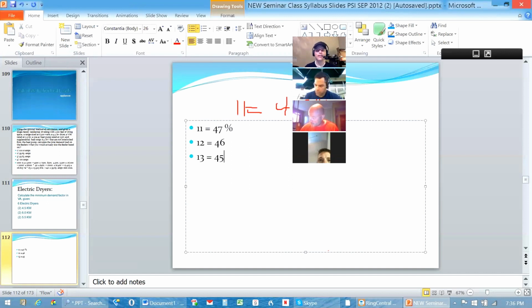So I'm just going to take the net number. If they gave me 18 dryers, for example, I'm going to have to subtract the initial 11, which is where the table stops and starts that funny math. So that's a balance of 7 additional dryers. 18 minus 11 is, in fact, 7. Each one of those dryers is going to subtract 1% from the level that we started at, the 47%. So it's really 7 dryers, each one being 1%, so 7% is what we're looking at. That's going to be subtracted from the 47%, which is what 11 dryers would be. And so I end up adjusting my value to 40% of the nameplates.